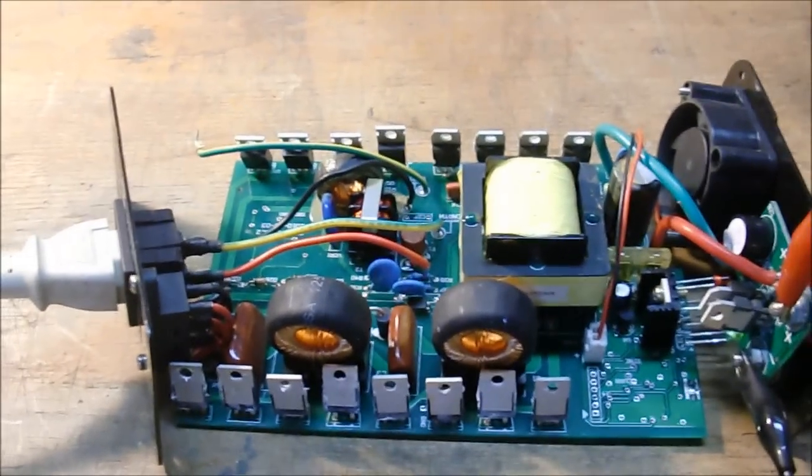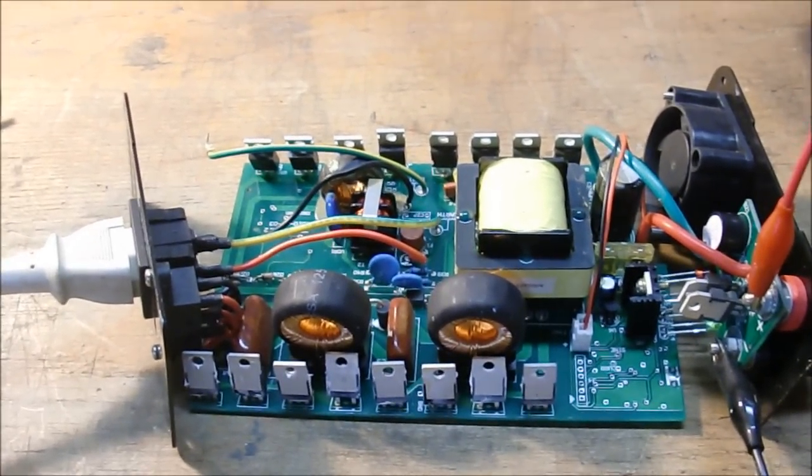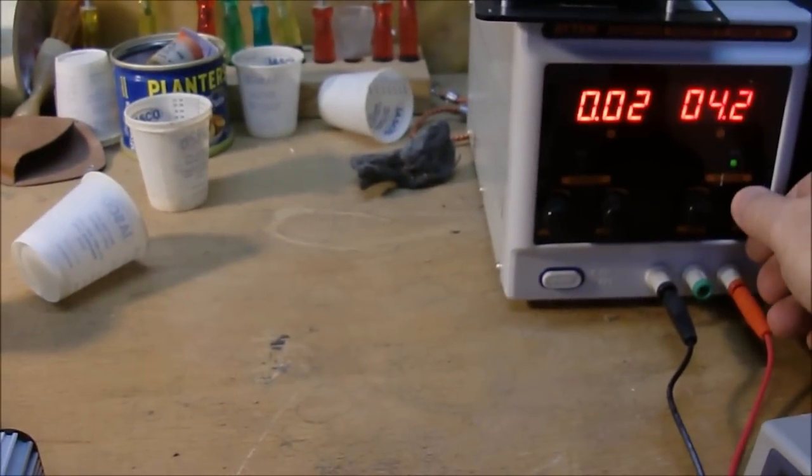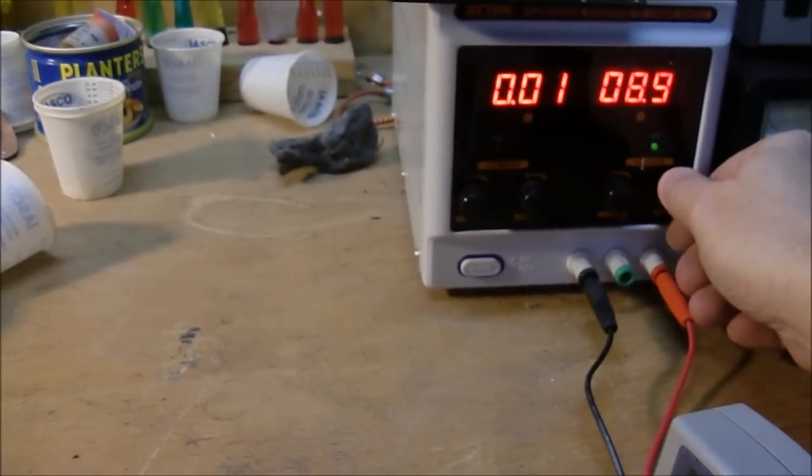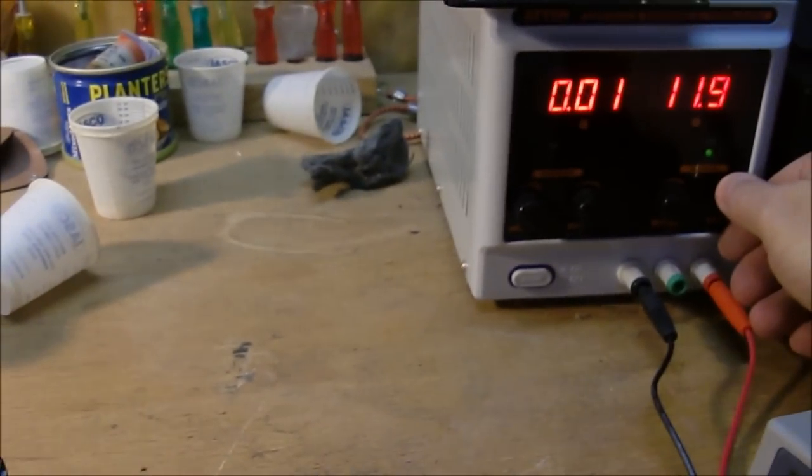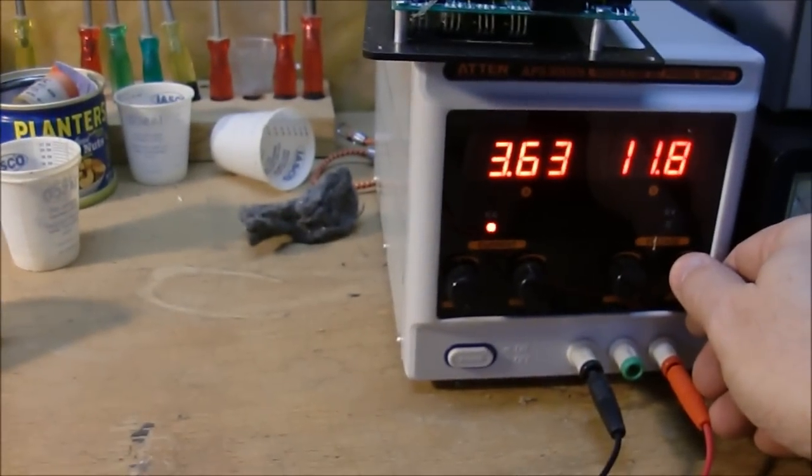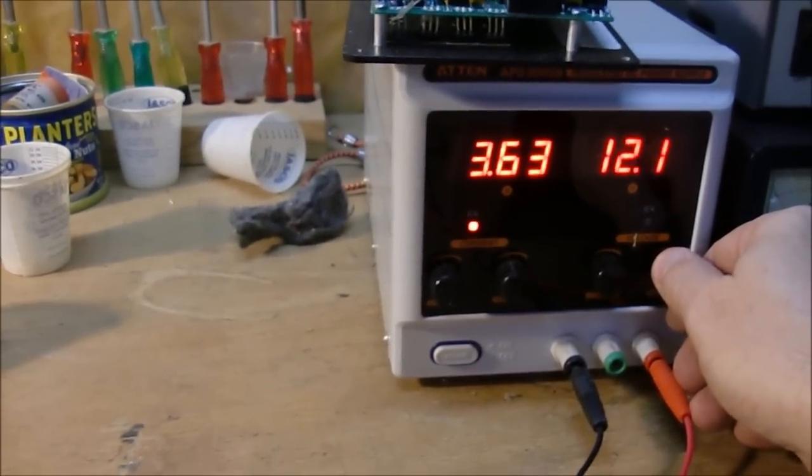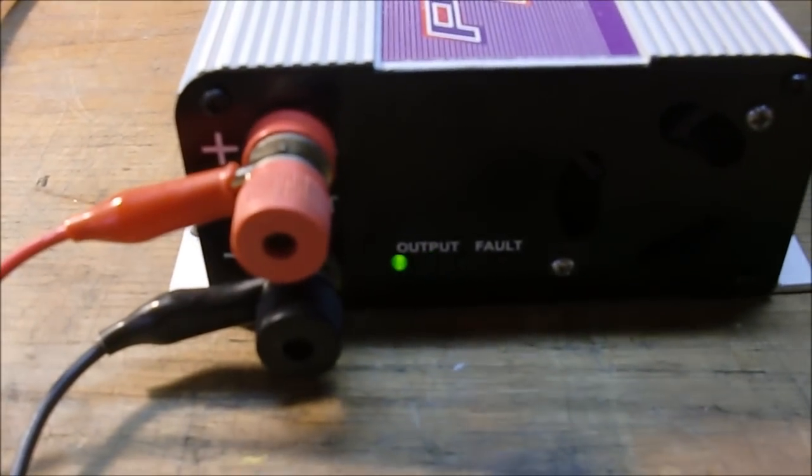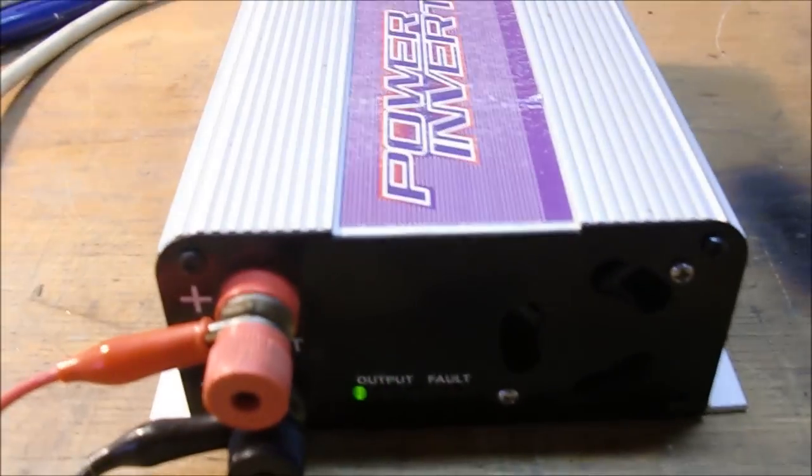I'll button it back up, run it on my system for a while, and then move on to the next one. Got it all buttoned up. We'll do a final check here. Start cranking up the voltage. The red light starts blinking at about 7 volts. Light goes out. Starting to boogie. Reading 34 watts, 3 to 4 amps on the meter there. We're good to go.